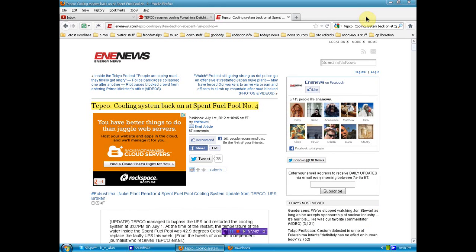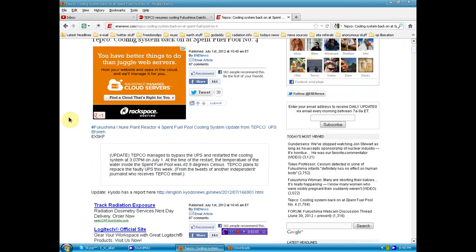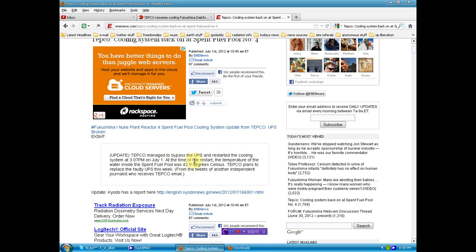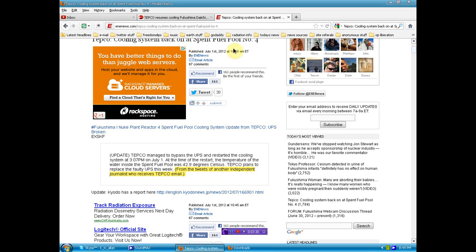Starting off, the first bit of information I found, which is basically the same as what I just told you. Tepco managed to bypass the UPS and restart the cooling system at 3:07 p.m. on July 1st. At the time of the restart, the temperature of the water inside the spent fuel pool was 42.9 degrees Celsius. Tepco plans to replace the faulty UPS this week. From the tweets of another independent journalist who reads Tepco email. I can't verify this. I'm going to share it with you.